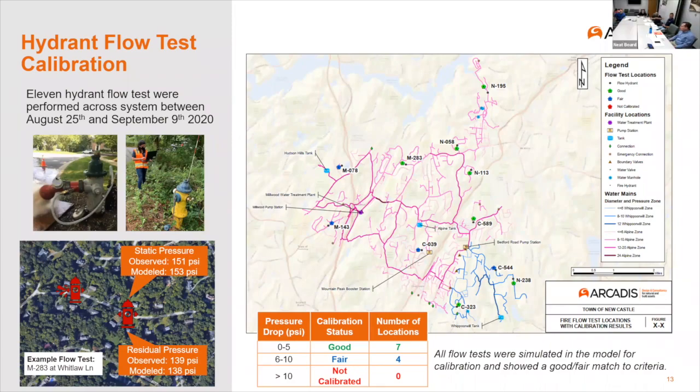Right. That was my question. It was just driven to see if there were actually substantiated GPM flows in some of these tests and some of this modeling. Yes, but you would need to take it down to 20 psi to get the maximum available fire flow. Presumably you would need a pumper truck, right? Yeah, if it's 150 psi hydrant static, then you would have to put it into a centrifugal pump. That's one way. That was exactly my question.